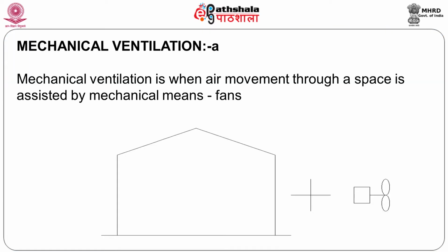Second thing is, there is a certain amount of legislation which has come in today, which blindly says that you should have a certain amount of air changes for an application. The National Building Code, for instance, will specify that stores and warehouses should have 8 air changes per hour. You might find a specification to say that you need for a workplace minimum 10 air changes per hour. Now such requirements cannot be met by natural ventilation. At that point of time, you have got to look for supplements like mechanical ventilation.